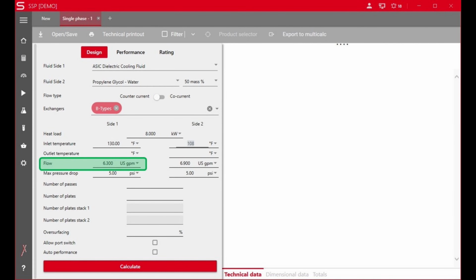On the other side of the heat exchanger, using our hand calculations, maybe the maximum temperature coming off your dry cooler on a hot day is 108 degrees, and the pump flow rate is around 6.9 gallons per minute. Now, this is about all you can enter. You need to leave at least one box open on both sides of the calculator so the tool doesn't become over-constrained and give you an error.